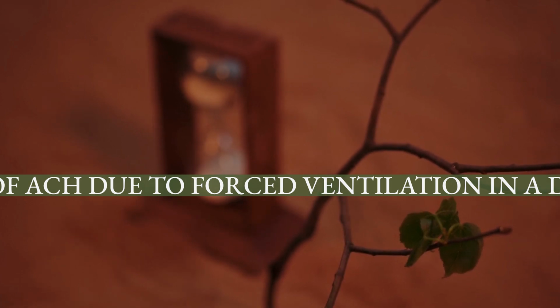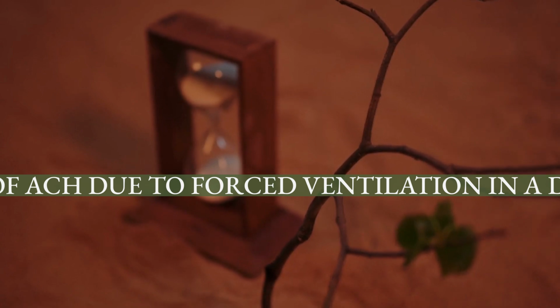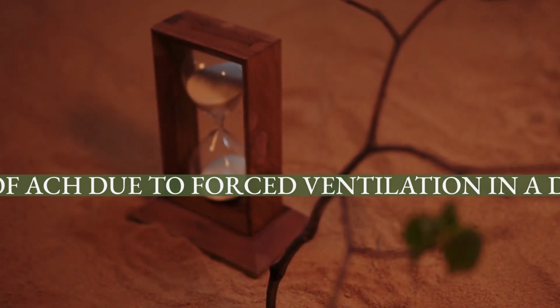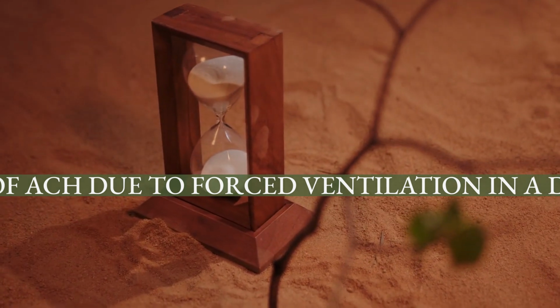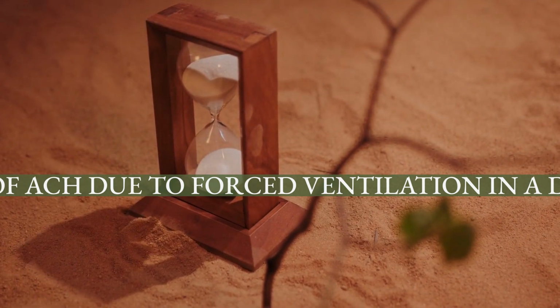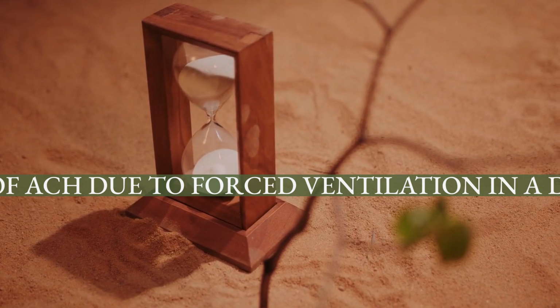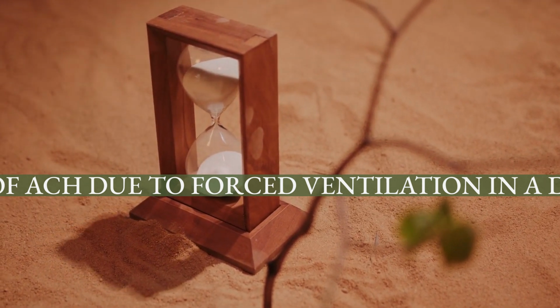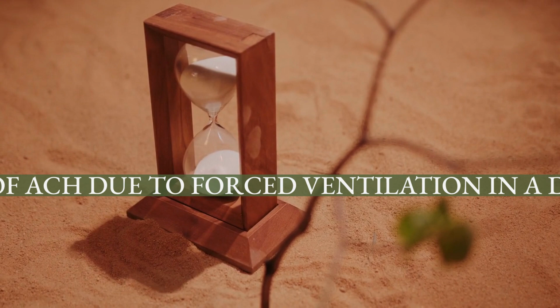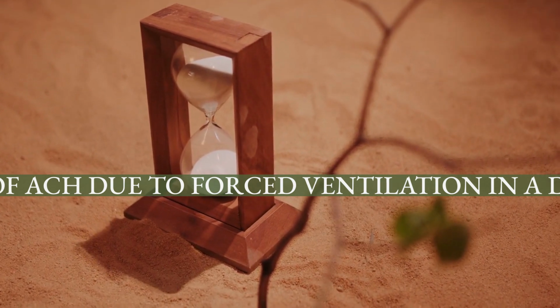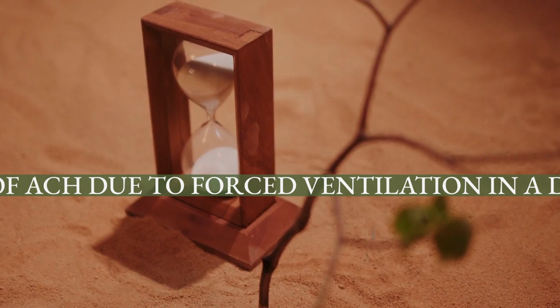For example, to maintain 15°C temperature in a certain dwelling, about 3 kWh of heating are required at 0 ACPH. No heat loss due to warmed air leaving the dwelling. Instead, heat is lost due to conduction or radiation. 3.8 kWh at 1 ACPH and 4.5 kWh are required at 2 ACPH.